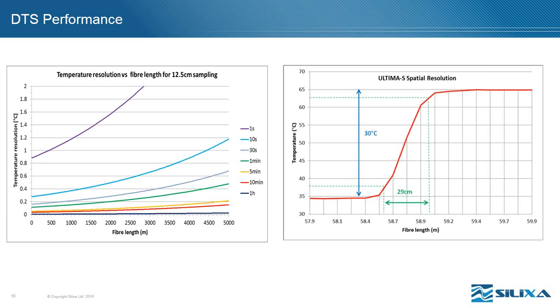It defines the ability of the instrument to detect accurately a temperature event. This graph shown on the right of the screen is taken from our test facilities, and this is what we do to characterize the spatial resolution of the unit. It's quite different to the sampling resolution of the unit. Often it's about twice the sampling interval. So we use a hotspot, or a temperature event of about 30 degrees in amplitude, and we try to identify what is the length of fiber needed to detect this 30-degree hotspot. The data is shown here for the Ultima S. This is a 5-kilometer range DTS unit.